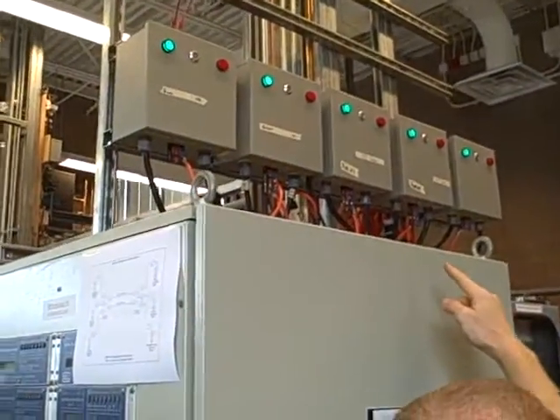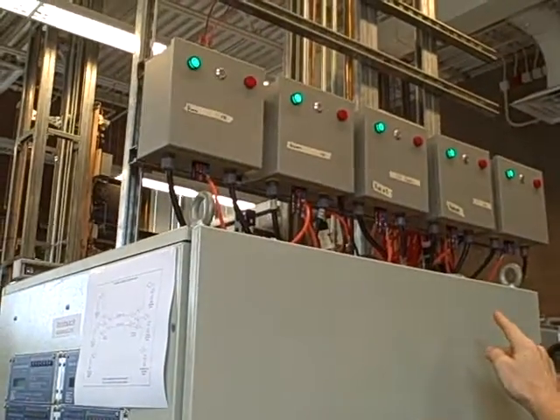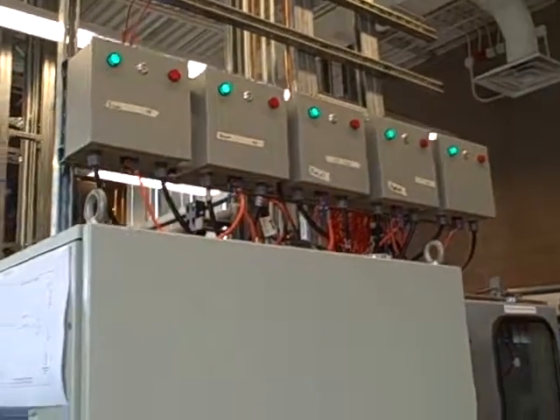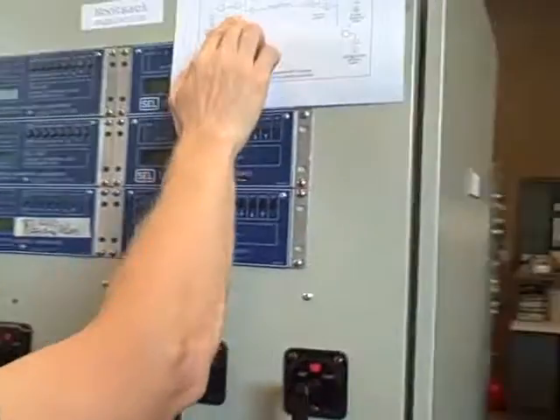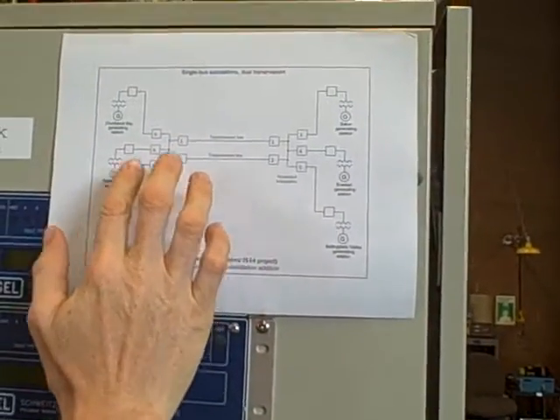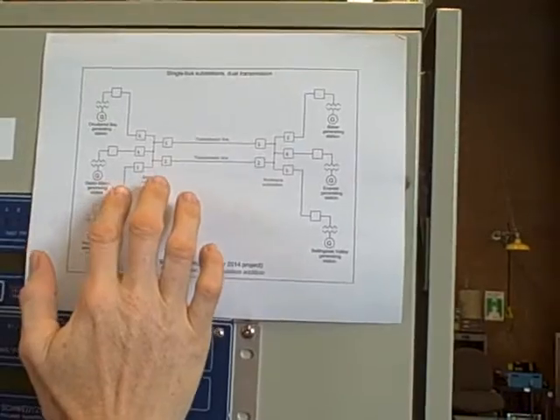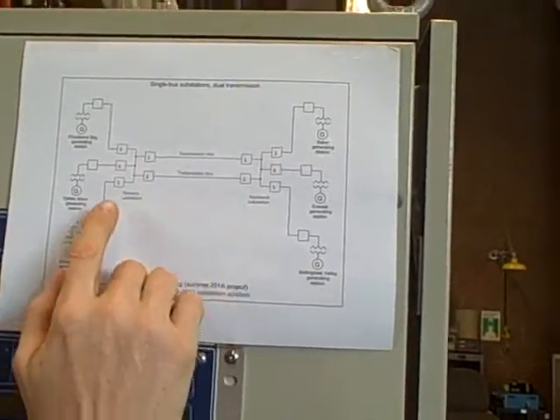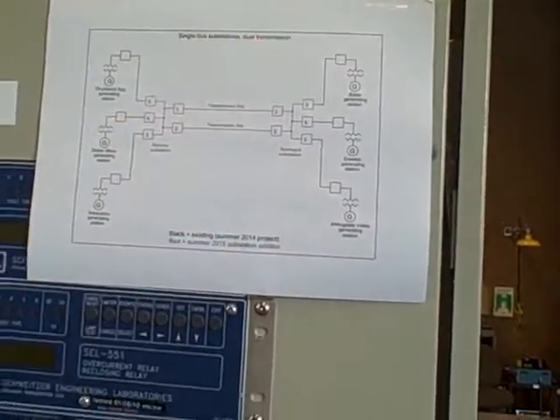If I go over here you can see now all my circuit breakers — all five of them — are showing green. They used to be all red, they're now all green. That is how our single bus protection scheme works: if there's any differential current detected on that bus indicating a fault within the bus, the only way to guarantee we clear all power to that faulted bus is to trip all five circuit breakers, which is what our lockout relay is doing.